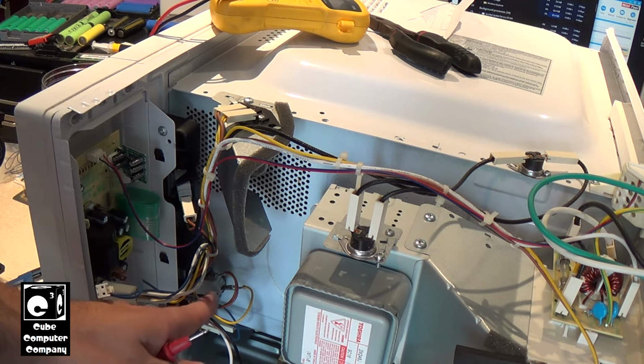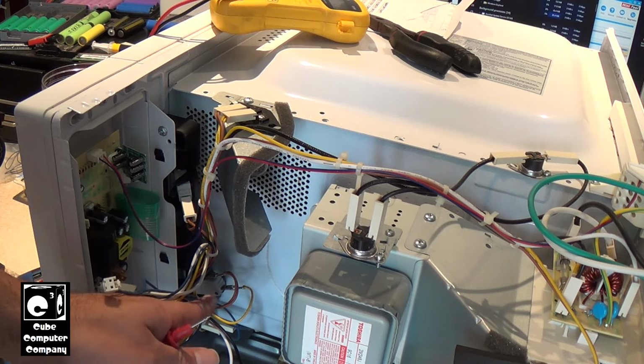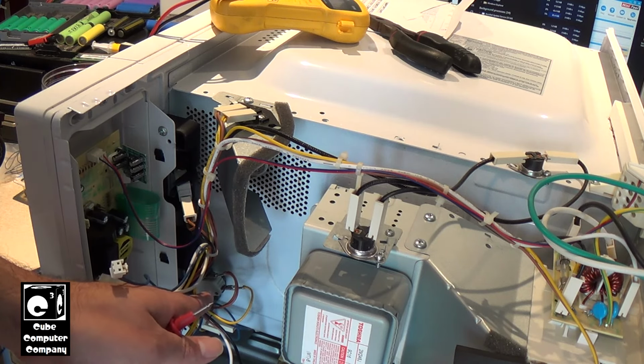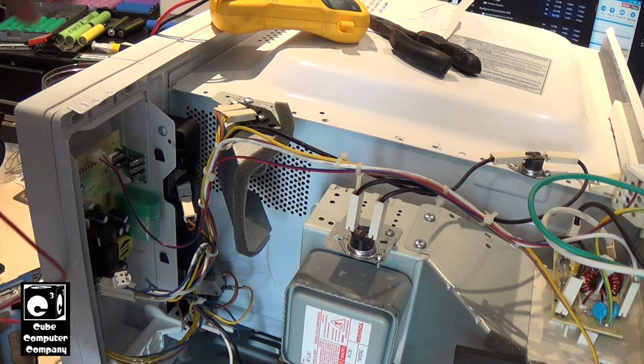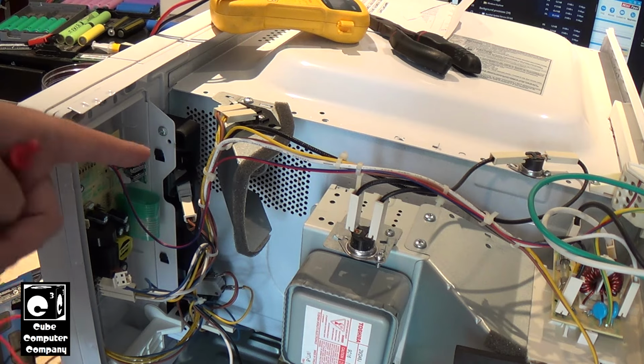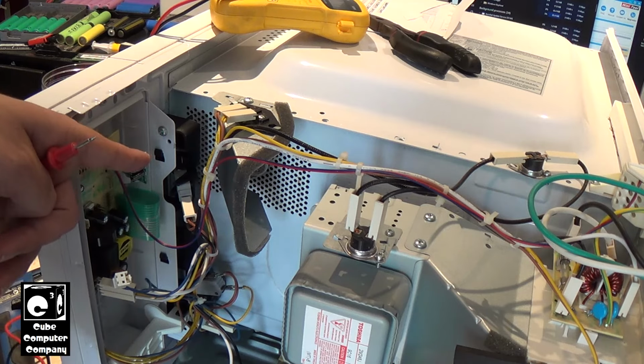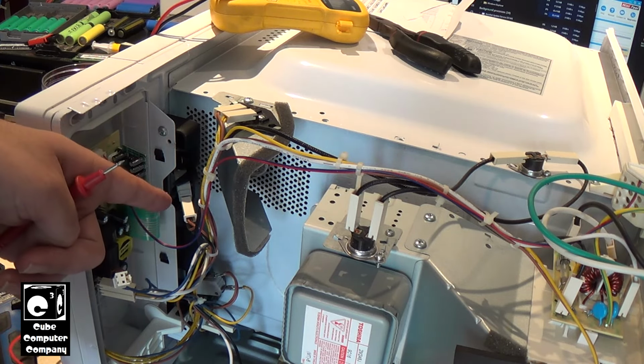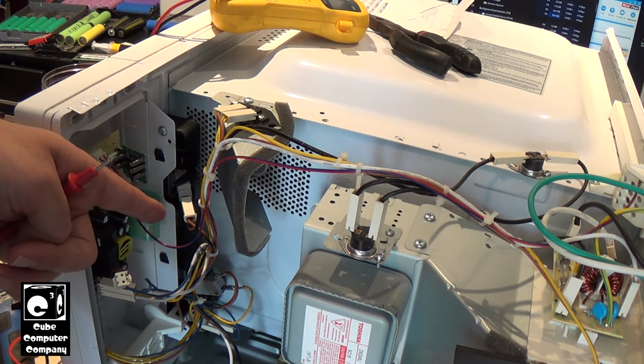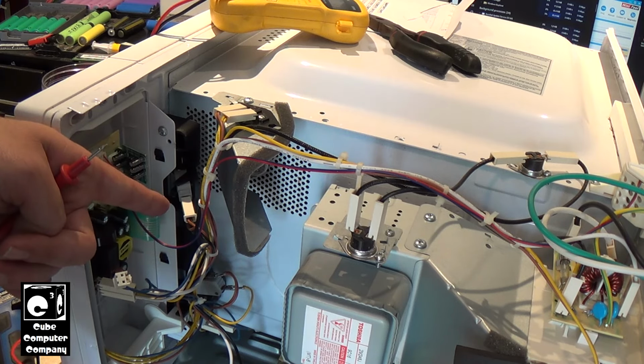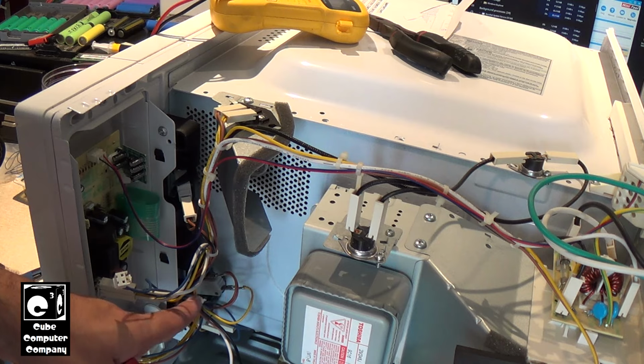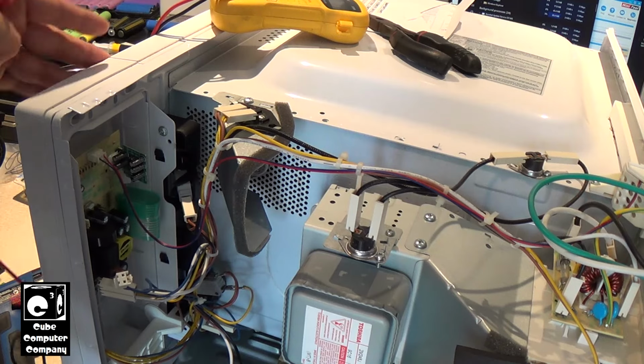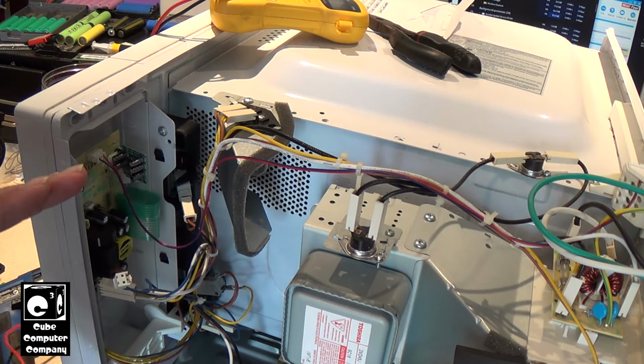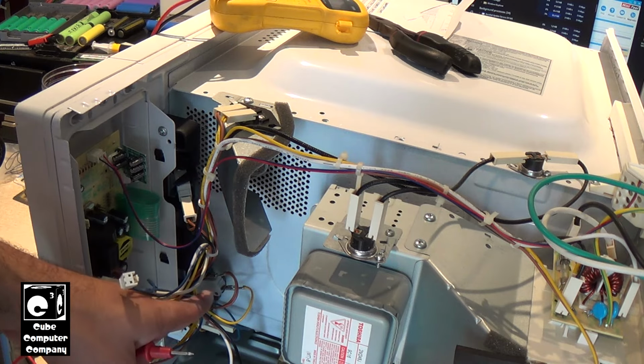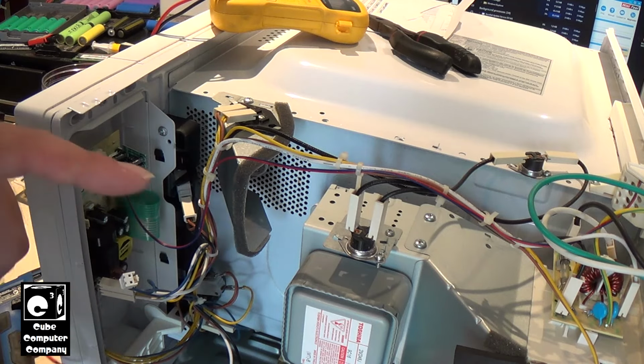That's why we have the monitor switch. The monitor switch also monitors the status of the door, and let's say for example this switch does not work properly. So normal open, meaning that when the little push button on the switch itself is not pressed in, which is when the door is open, this switch shall be open. Okay, let's say for some reason it does not open. That's why we have the monitor switch. That one's normally closed. So when the microwave door is closed, that switch is open. That switch there basically is tied between live and neutral. Yes, live and neutral of the incoming power.